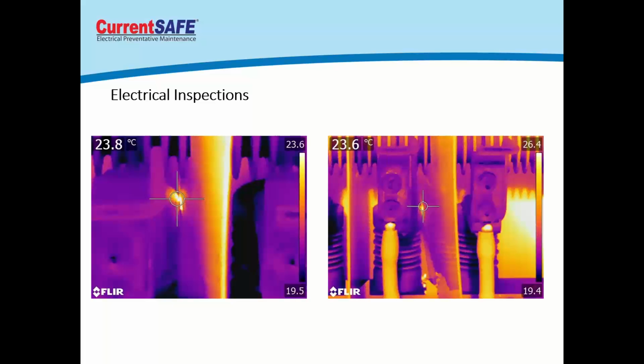So this medium voltage switch is upwards of $50,000 if you had to replace it and buy it new. So this is another great reason why you spend a couple of grand, $2,000 on labor and equipment to clean and do some repair, and now we don't have an anomaly building up in a cabinet that's working towards a failure point. And we've saved a distribution system and an unplanned outage with that. So there are great benefits there.